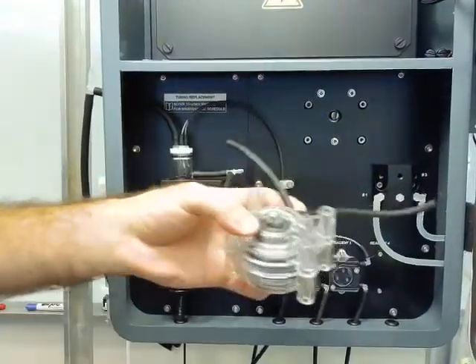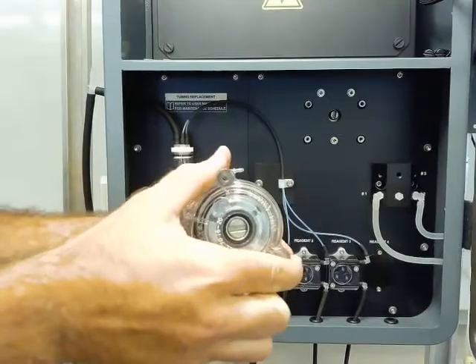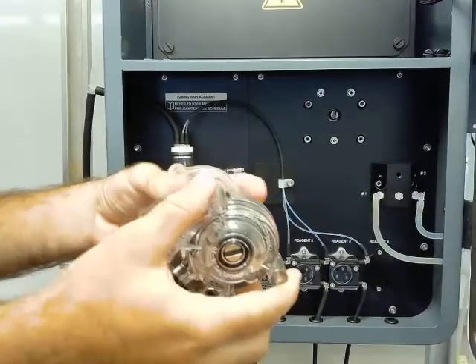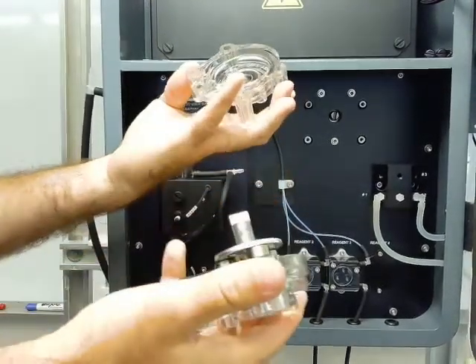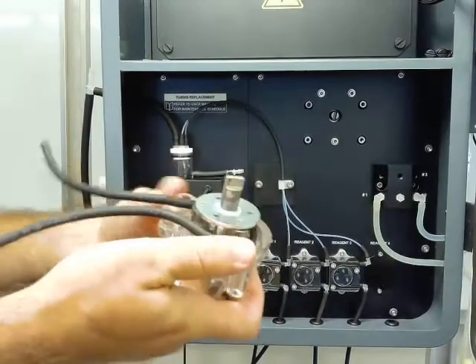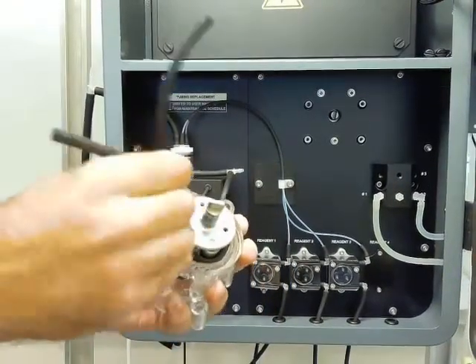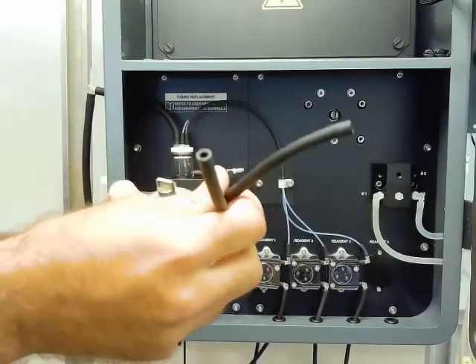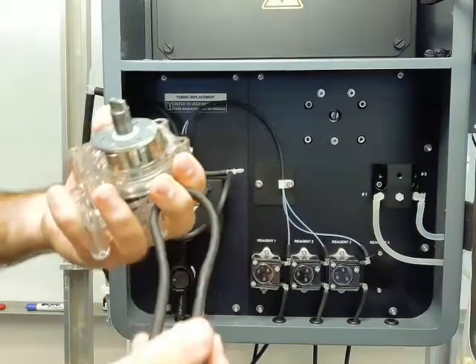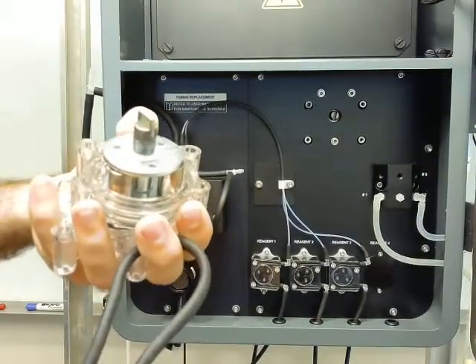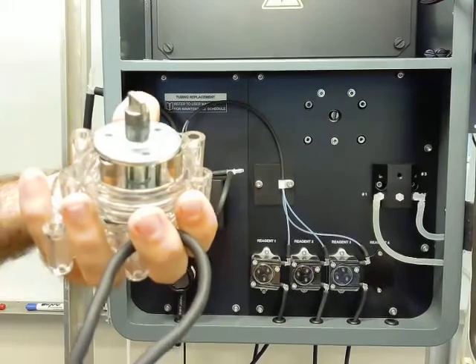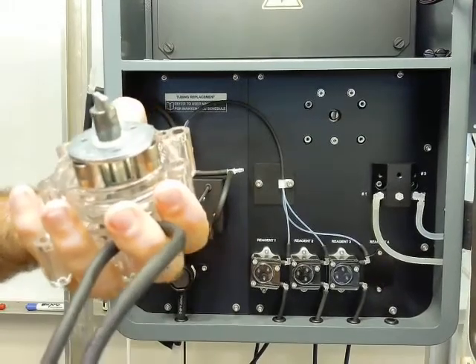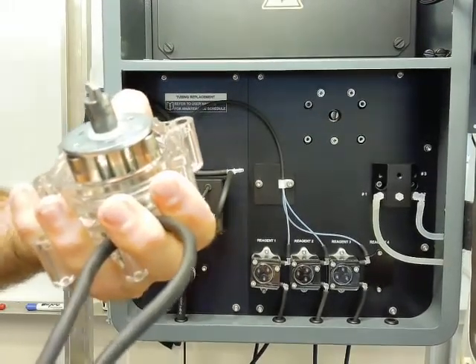So once we take off the tubing from the selection block and then the mixing loop, we can take the whole thing and just take the two halves apart. Again, these plastic halves are identical, so you don't have to worry about that, but we can see that the rollers do have to go in one way. So once we pull out the tubing, you might be able to see a little bit, and this one's been in operation for a little bit, starting to flatten out a little bit. Again, this is normal after maybe a couple weeks' worth of runtime.